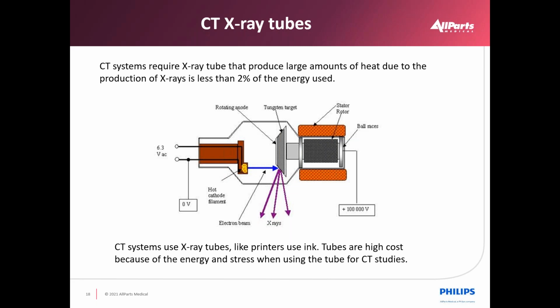So as you can see, the hot cathode filament, we control the temperature of that filament. And in those changes of controlling the temperature, we control how many electrons are produced. And that controls how much current's flowing through the tube and how many X-ray photons are produced. So the high voltage accelerates the electron beam from the left here, in this case, to the right, which is the anode. So we'll have a potential of up to 140,000 volts.